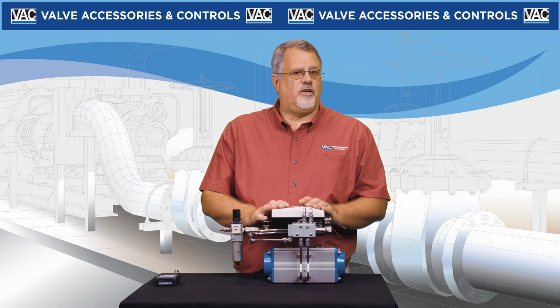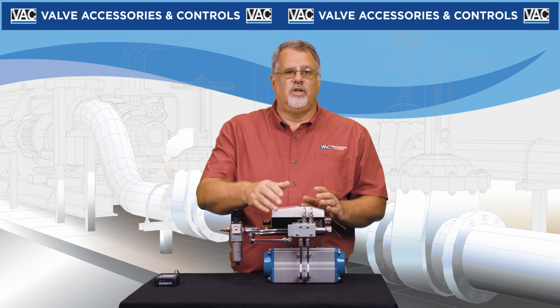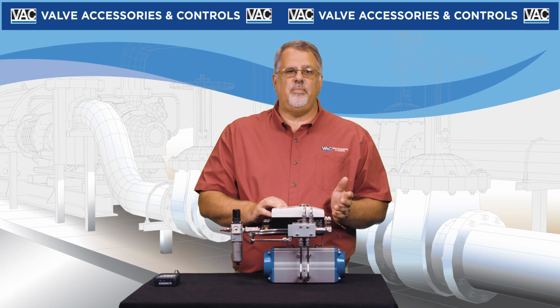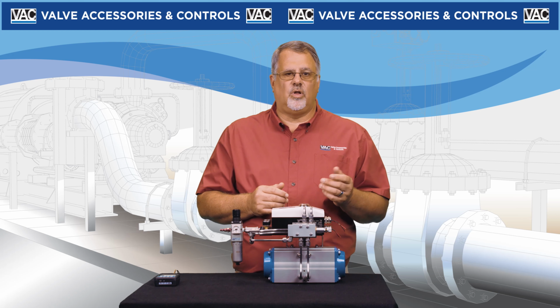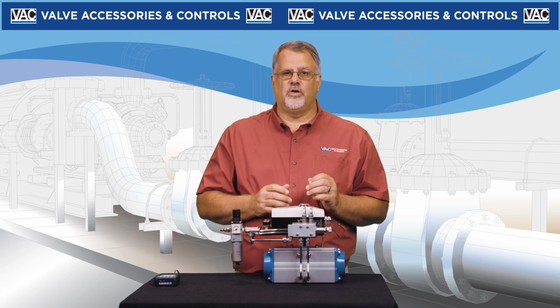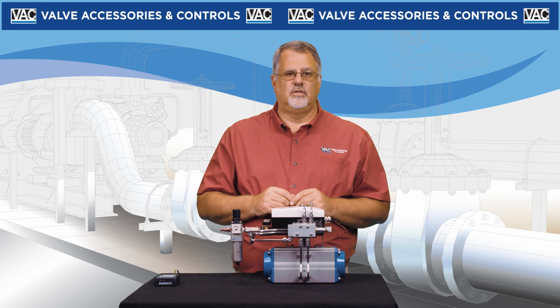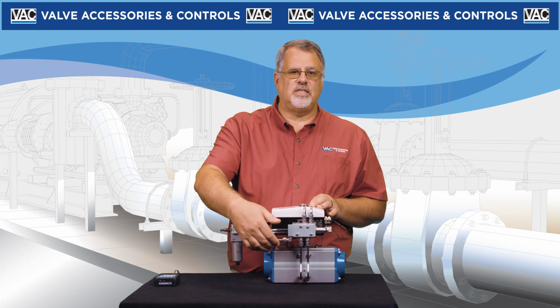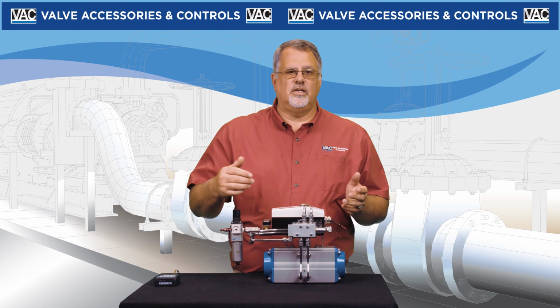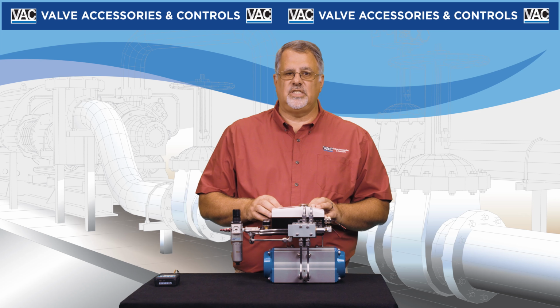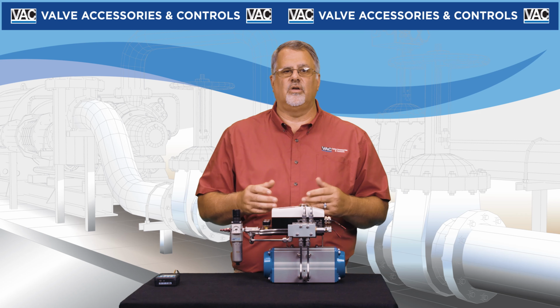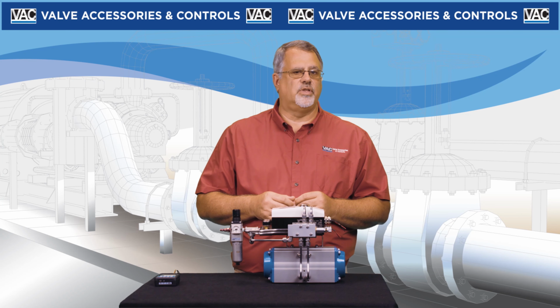This is a fail-freeze valve positioner with a pneumatic lockup valve. The positioner contains a special I2P module and a pneumatic relay that will hold the air pressure in the actuator upon loss of the electrical signal. The pneumatic lockup valve has a sensing line here and an adjustable spring that allows it to be set to lock the air into the actuator when the supply pressure falls below the desired set point.